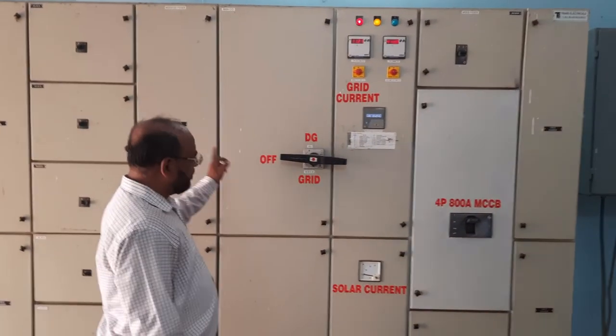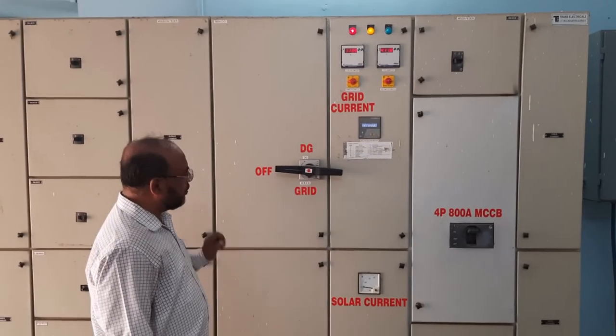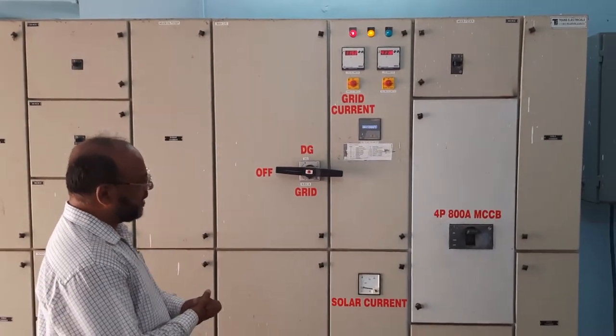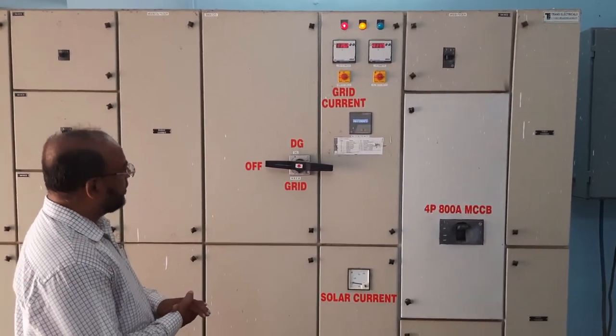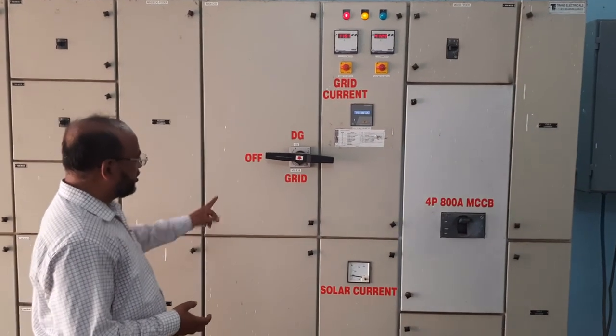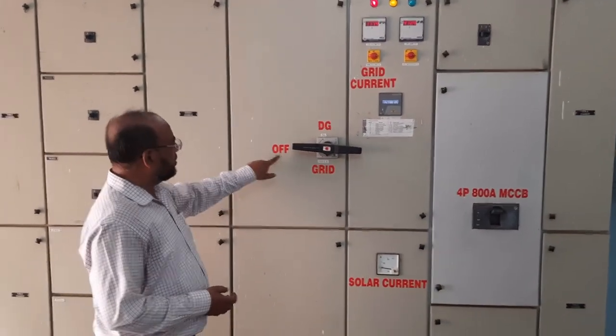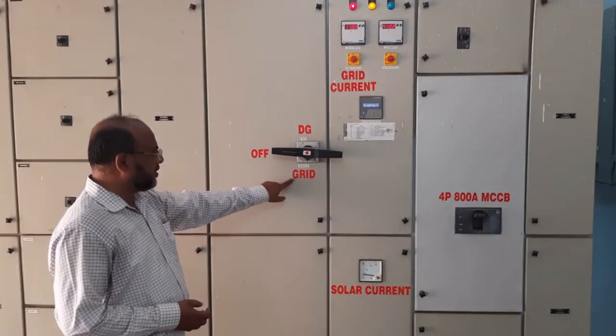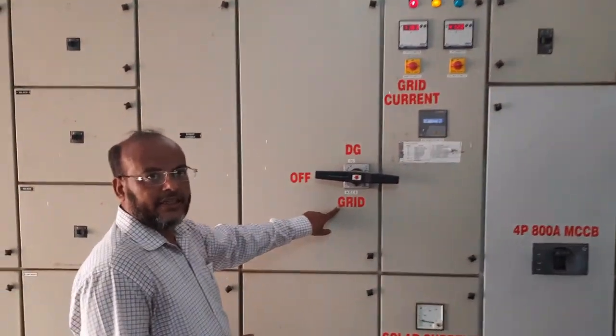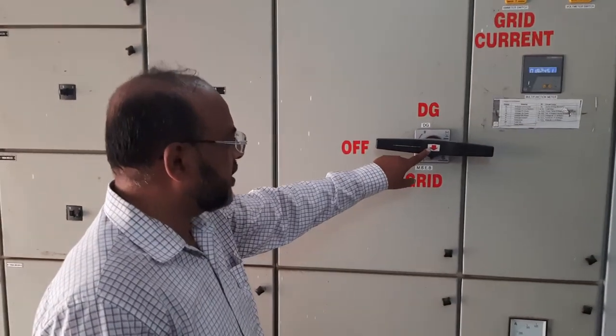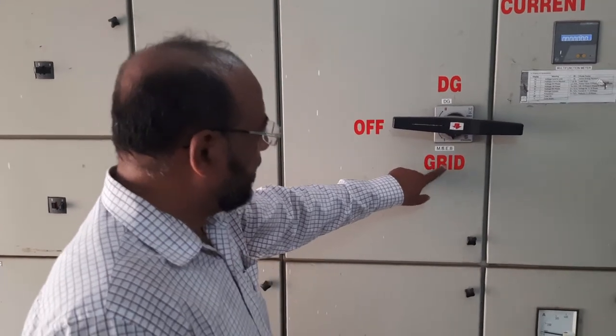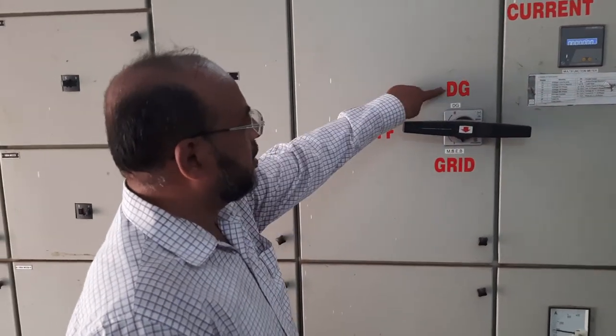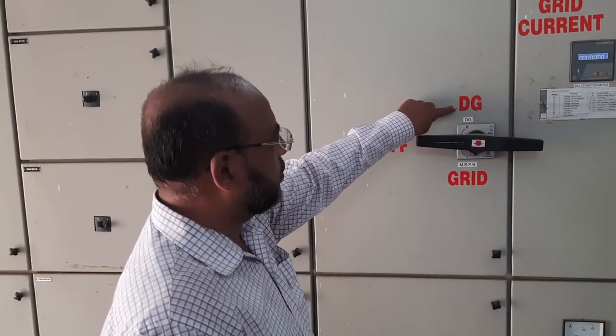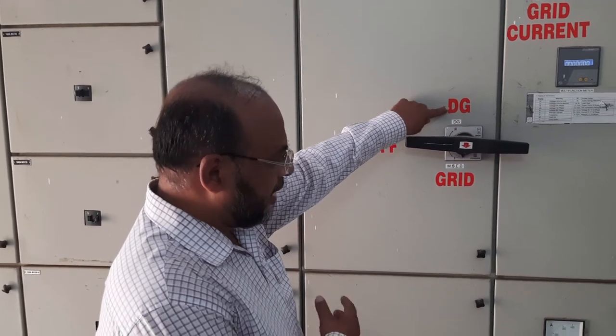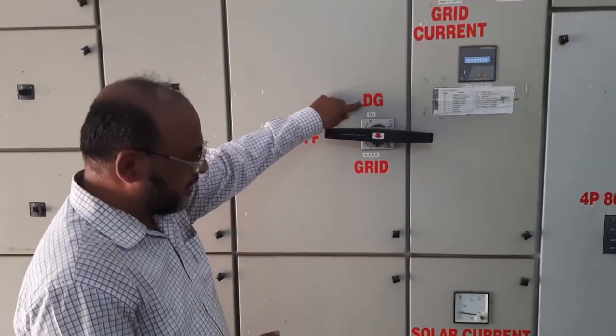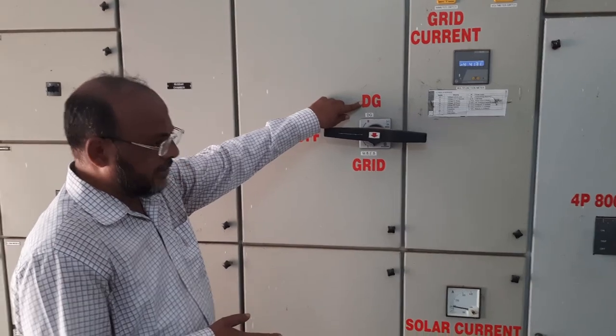This is the main panel. It comprises a solar 800 ampere MCCB, some metering units, and a changeover switch. This is the off position, and this is grid. Presently the grid supply is there, so the switch is connected to grid. When the grid fails, the switch is changed to the DG set, and the college will get the supply from the DG from here.